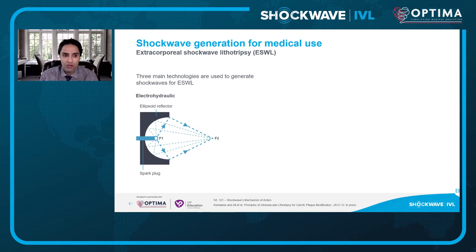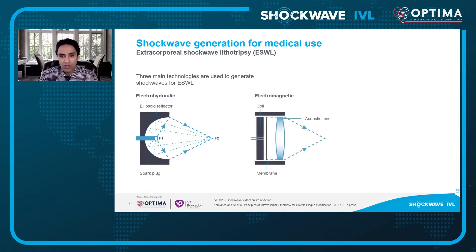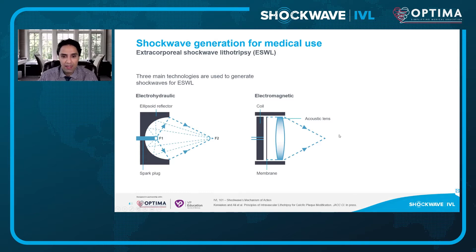Electrohydraulic energy is the important one because that's predominantly the one used in shockwave IVL. There are other methodologies, including electromagnetic. In an electromagnetic system for shockwave development, you have an electric coil, and as that coil generates energy, it bends a membrane — kind of like a dome — just in front of it, creating a focused energy which is then focused either by a parabolic reflector or by a lens that focuses the energy into increased amplitude.